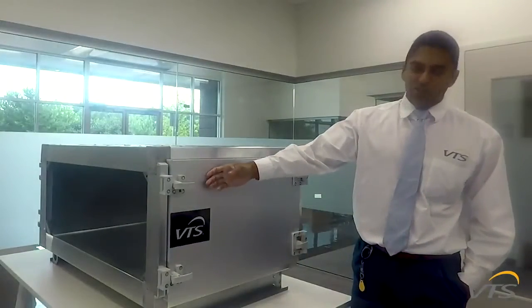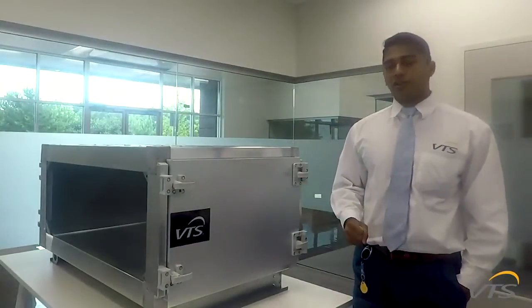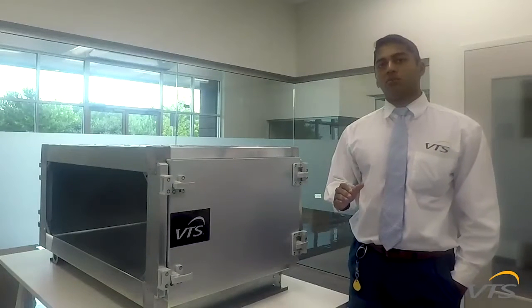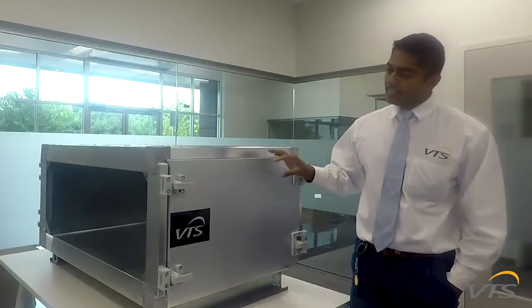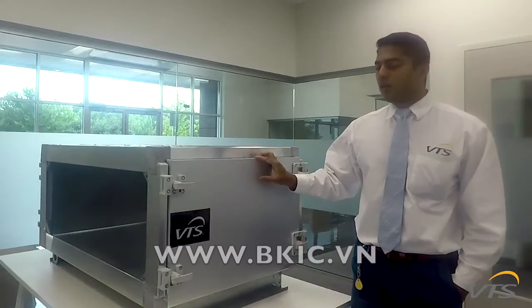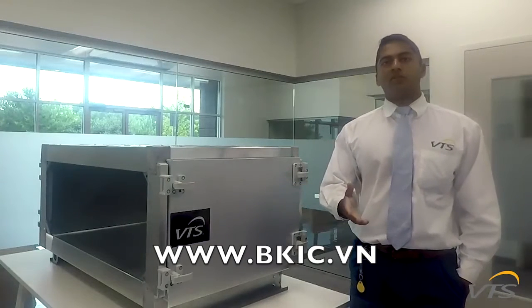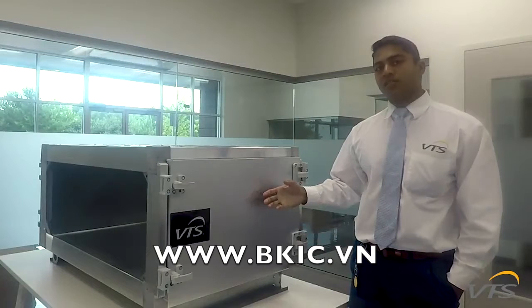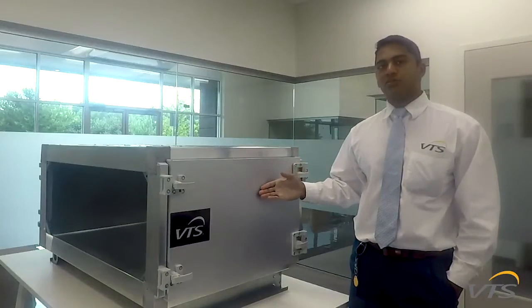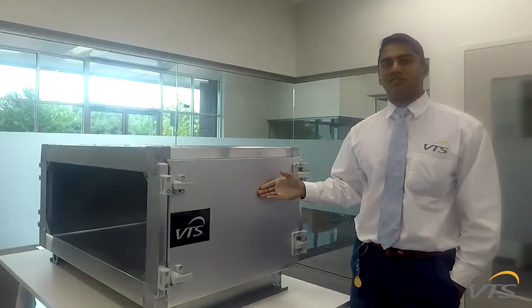As you can see here, there's a coating that we apply to all of our units, and this is standard across the board, both indoor and outdoor. It's an alu-zinc coating, which is pretty similar to your galvalume, and it's a hot dip process that achieves a 2,000 hour salt spray resistance on each of our cabinets.